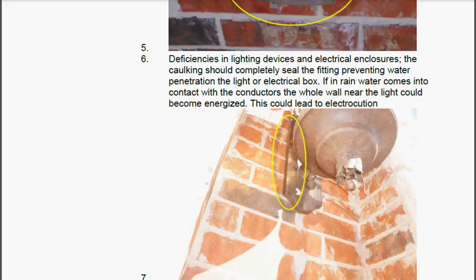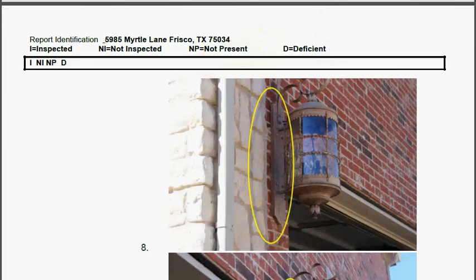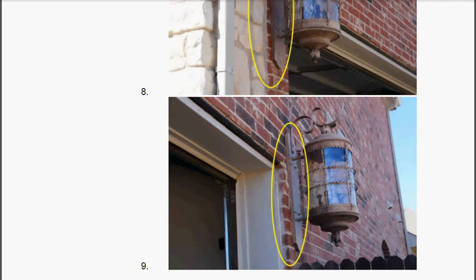The lights on the walls on the exterior need to be caulked. Basically, what happens is water gets into the back of these lights and gets in touch with the conductor, and if it's raining it can actually energize the wall below it - you could touch the wall and get an electric shock. That's not good.